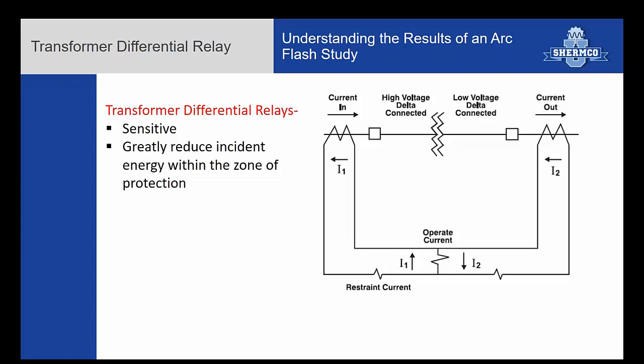Transformer differential relays are very similar. On transformer differentials, it's really power into the transformer should equal power out. In this case, they wrap the transformer differential from the high side breaker feeding the transformer to the main breaker, the secondary breaker of the transformer coming in. So it would greatly reduce the incident energy in this area between the sets of CTs. Transformer differential relays, and we're going to talk about others, are not easily modeled in most of the software today. Engineers have to do this outside of the software and then manually input it, so it's something that sometimes is missed. You have high incident energy levels in your study, but they might have missed that there are actually differential relays in your system.